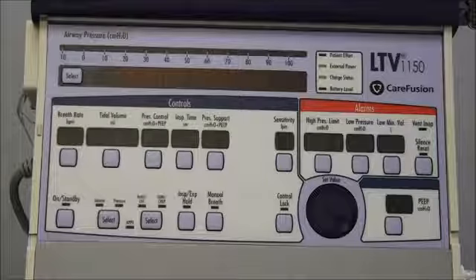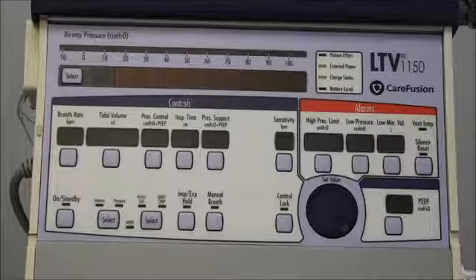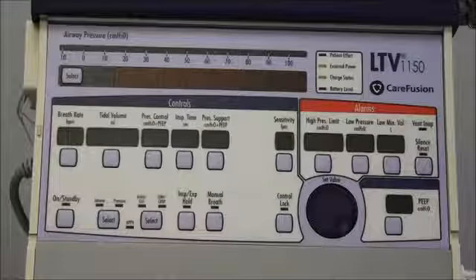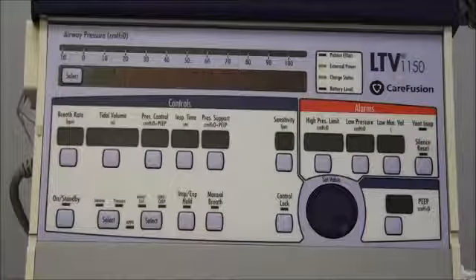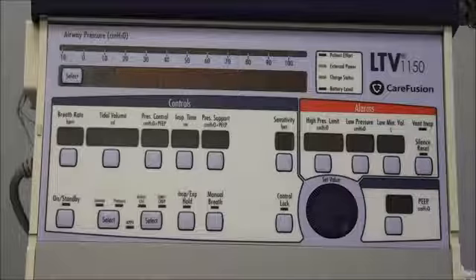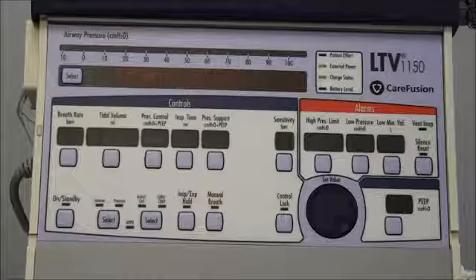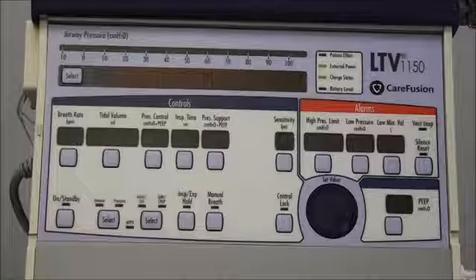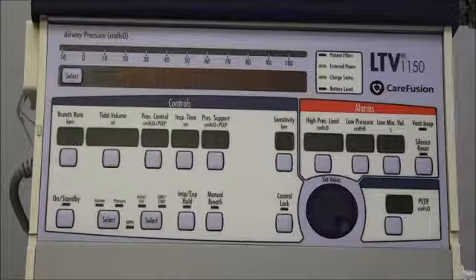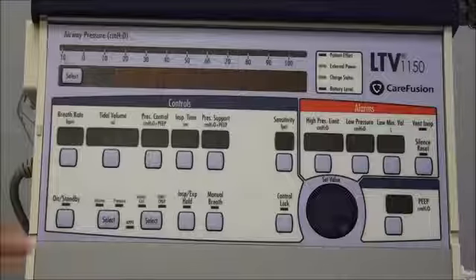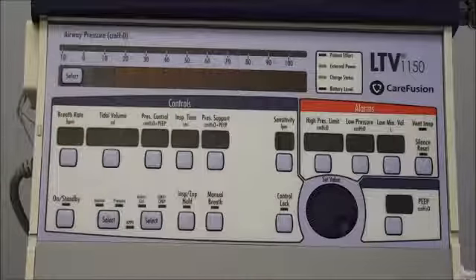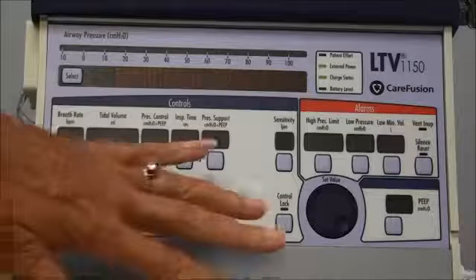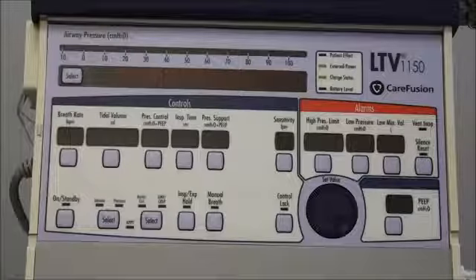Up above are the rest of your settings. The first one is your breath rate. So that would be ordered by your physician. It would just be prescribed how many breaths per minute that patient's going to receive from the ventilator. The next setting would be your tidal volume, and that would be the amount that the patient's getting for each breath. Next to that, you have your pressure control. So if you were setting a pressure on this, that's where you would set how much pressure the ventilator is going to be delivering to your patient. Next to that is your inspiratory time, and that is how long it will take that breath to go in. And then you have pressure support, which is another pressure setting.